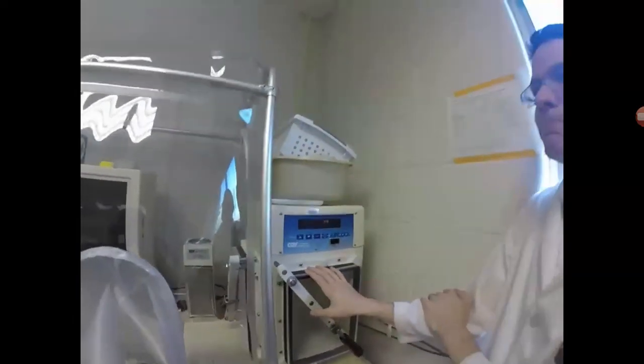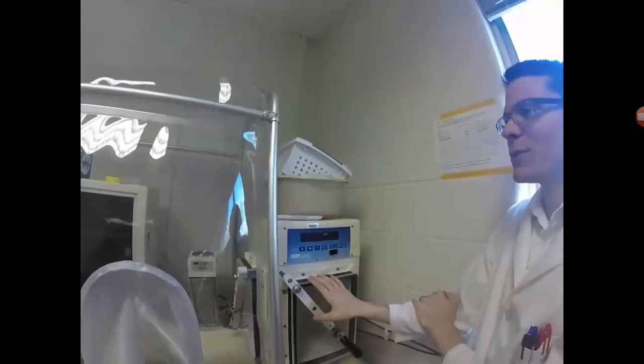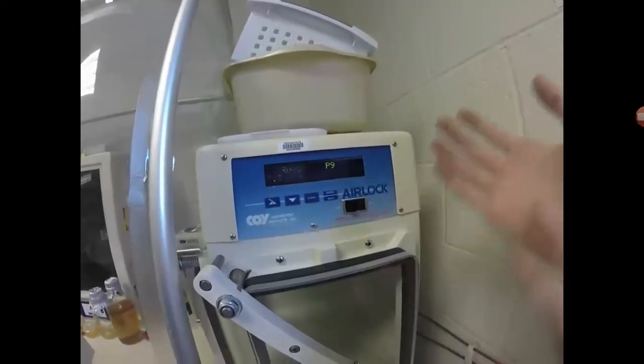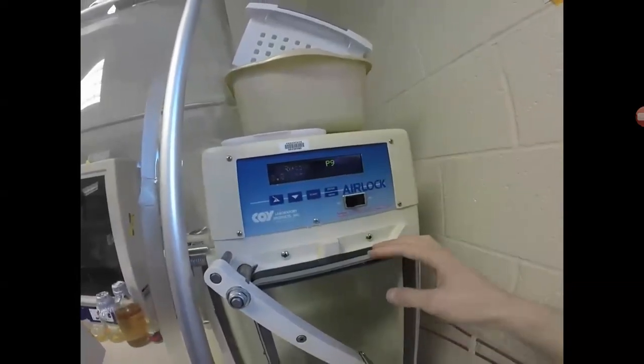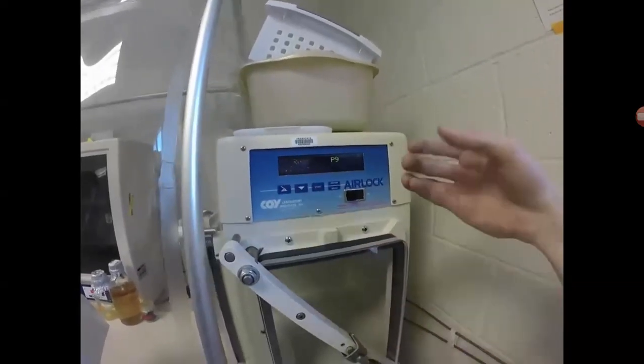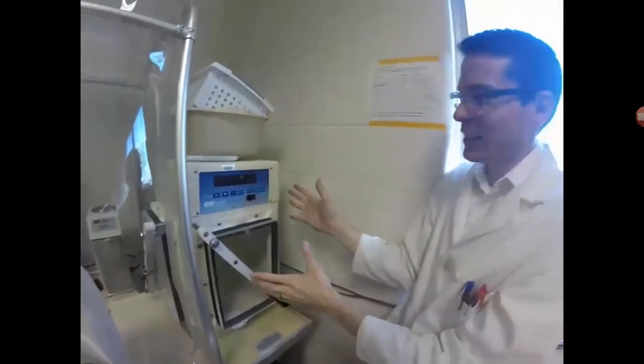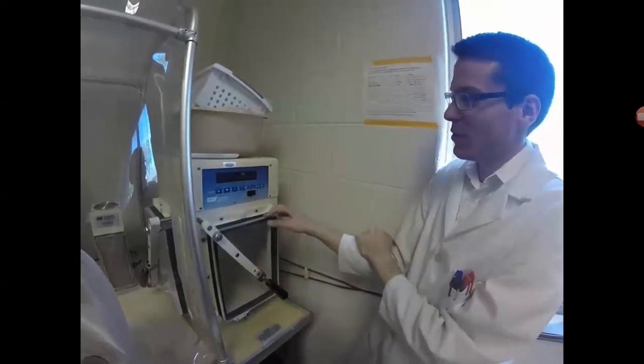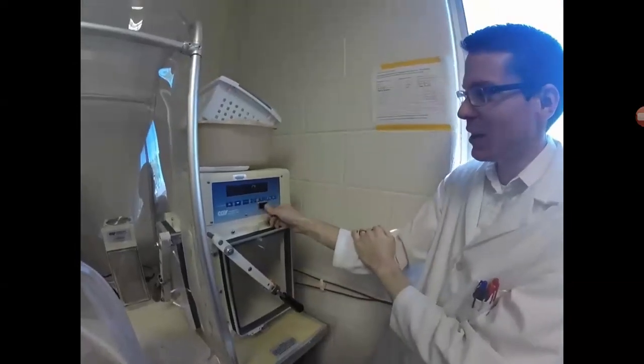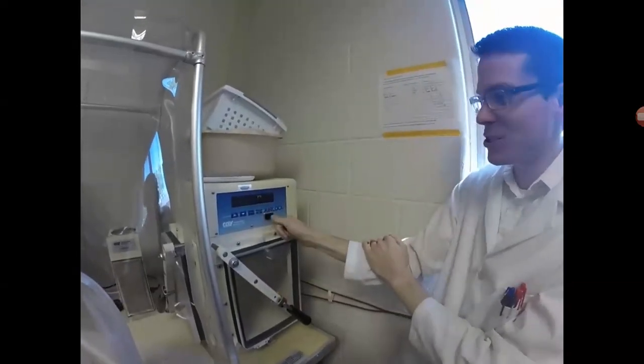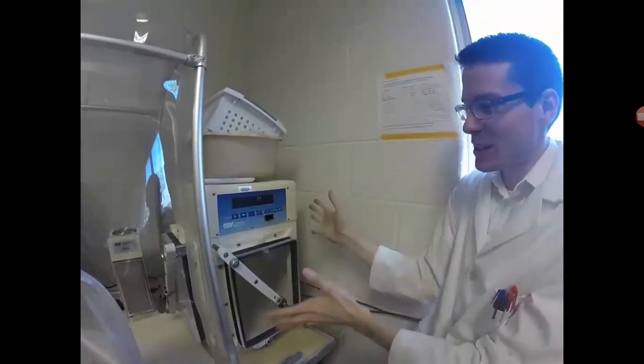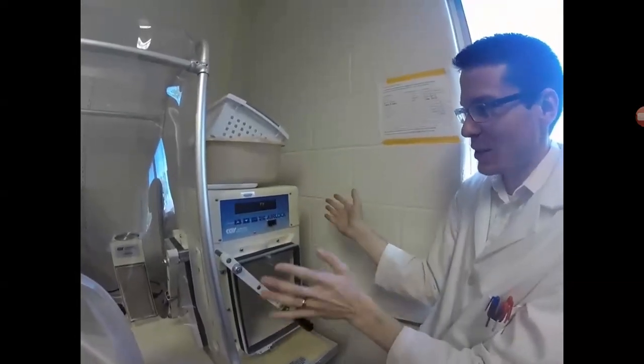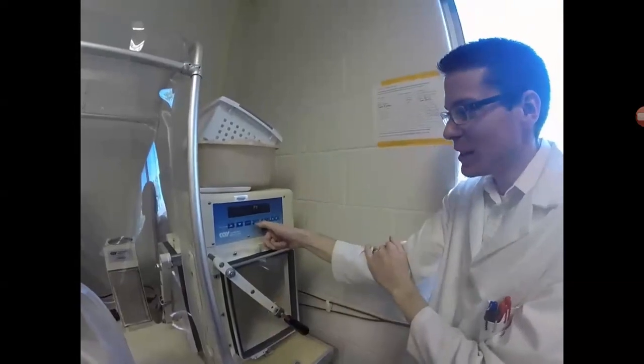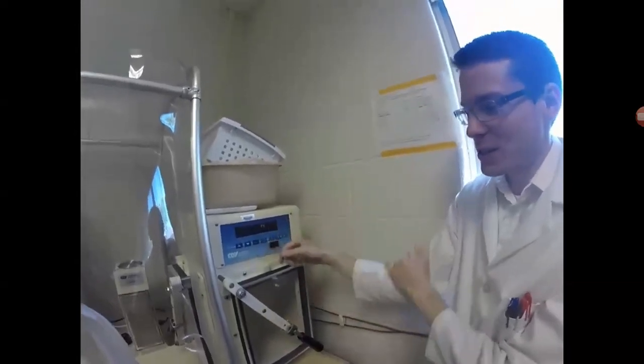Okay. Other than that, I think we're okay. What about the other programs, if anytime there's a problem? So let's say, for example, you put media in there that's hot and you're running the cycle and it started to boil. You want to immediately stop things and get the chamber open. So in order to stop a cycle in progress, the only way I know how to do it, at least, is to shut it off, turn it back on. That will immediately stop the vacuum or the gas purge, whatever it is. And at that point, then you can go back to the manual mode and adjust things accordingly.